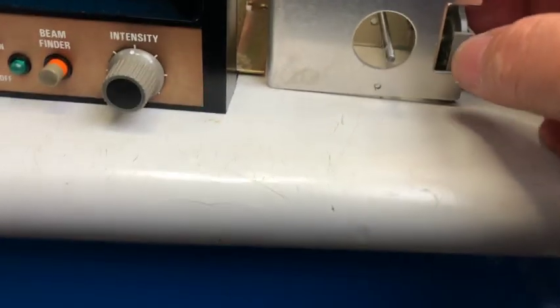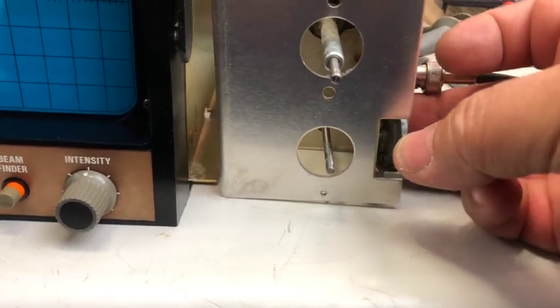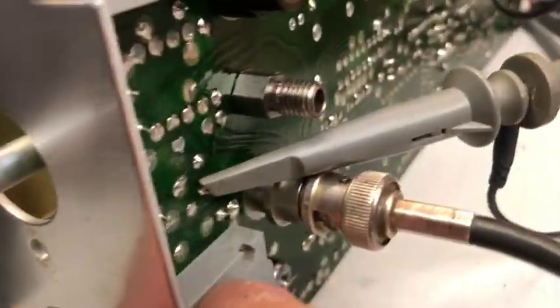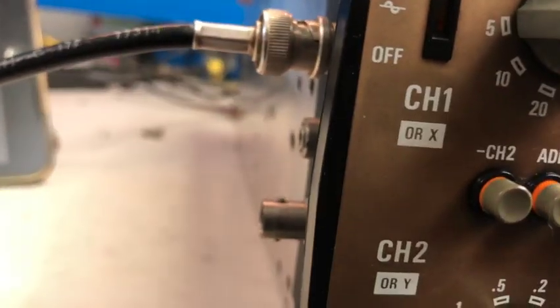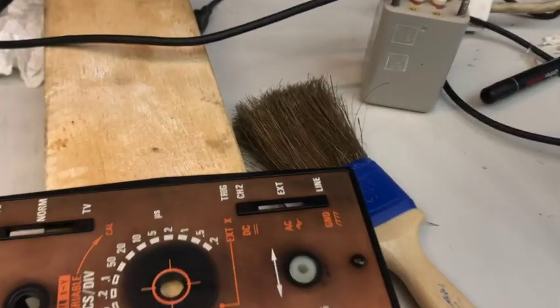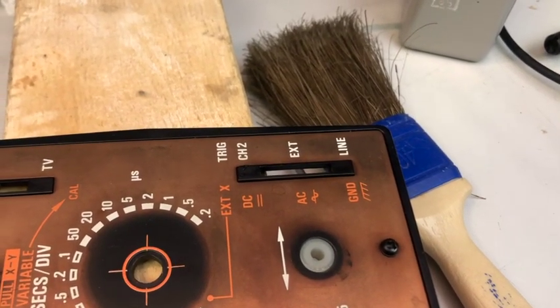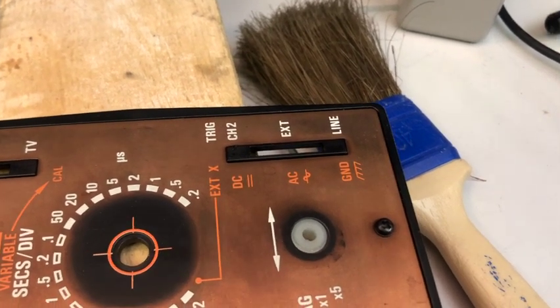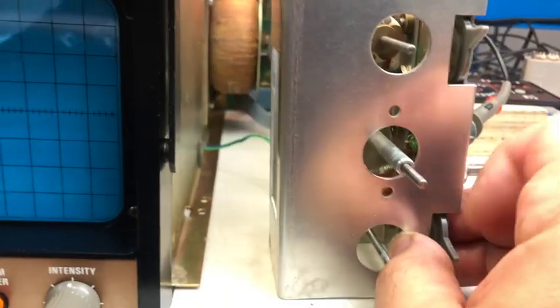So now, if I mount it back in the position and I hold it by hand, I now have signal to the base of the transistor that is inside there. Not easy to see. There is a transistor over there. So let's see if this will fix the triggering problem. Since the calibration of channel 1 does not include the channel 2 signal, since this triggering has been designed to work just with channel 2 or external, it's requested to feed an external signal in order to calibrate channel 1.